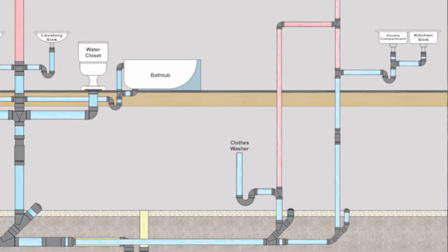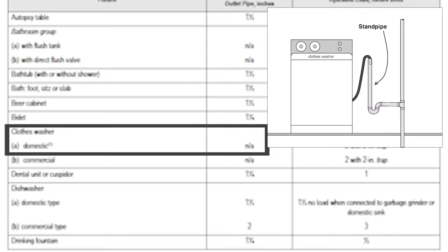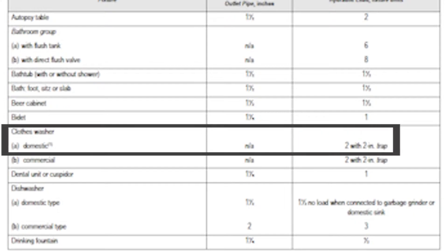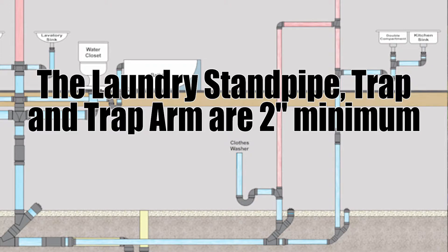The next fixture I want to look at is this clothes washer which is of domestic type. Notice the minimum size of fixture outlet pipe is NA or not applicable. That's because the manufacturer will build this pipe that comes out of the unit and it'll be of a varying size. However the hydraulic load is two fixture units if you have a two inch trap. This will have a minimum two inch trap. So this tells me that the laundry stand pipe, the trap, and the trap arm are all two inches in size.